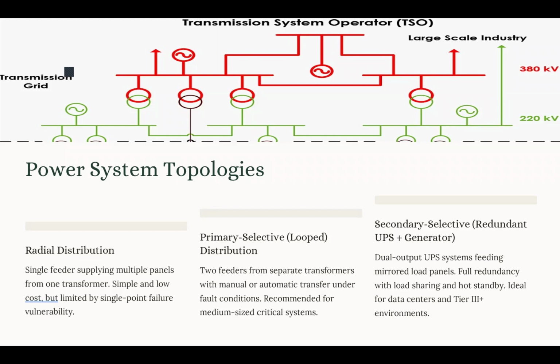Now, the radial distribution is a single feeder that supplies the power from one transformer to multiple panels, like in a tree-like structure. So it is the simplest and the lowest cost topology. It is a single point failure vulnerability, so any fault upstream affects all the downstream load. Normally, we use that type of topology in non-critical facilities or low priority zones, like office spaces or lighting system or low priority manufacturing areas.